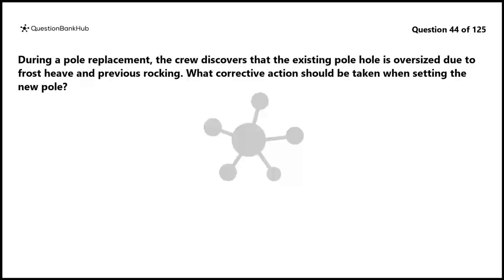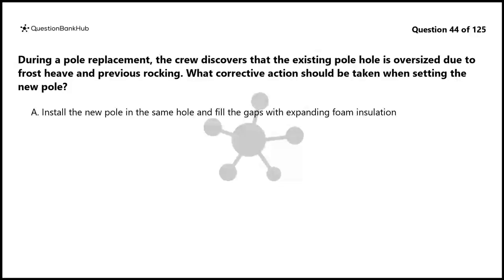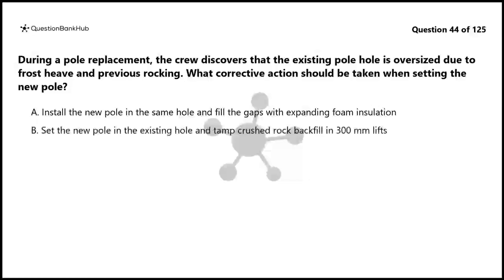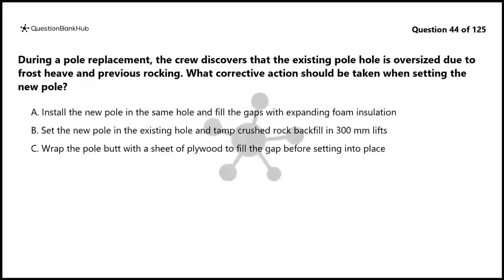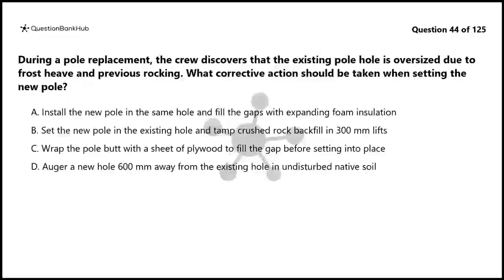Question 44. During a pole replacement, the crew discovers that the existing pole hole is oversized due to frost heave and previous rocking. What corrective action should be taken when setting the new pole? A. Install the new pole in the same hole and fill the gaps with expanding foam insulation. B. Set the new pole in the existing hole and tamp crushed rock backfill in 300 mm lifts. C. Wrap the pole butt with a sheet of plywood to fill the gap before setting into place. D. Auger a new hole 600 mm away from the existing hole in undisturbed native soil.